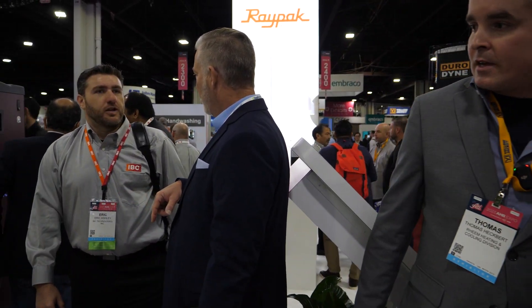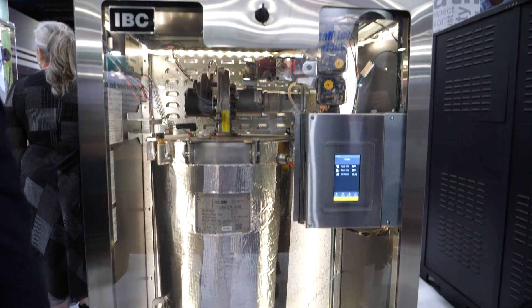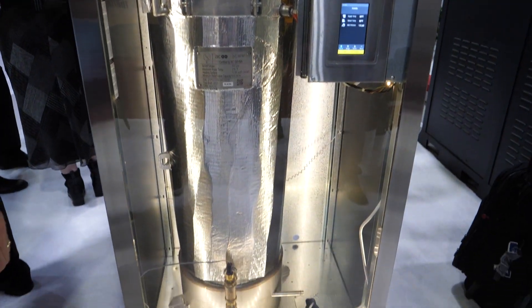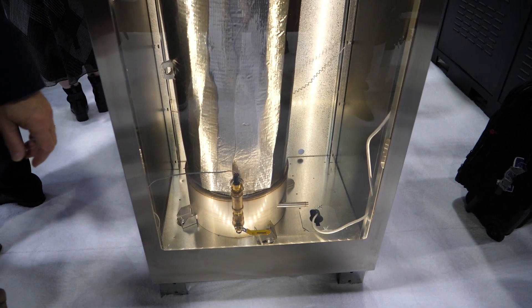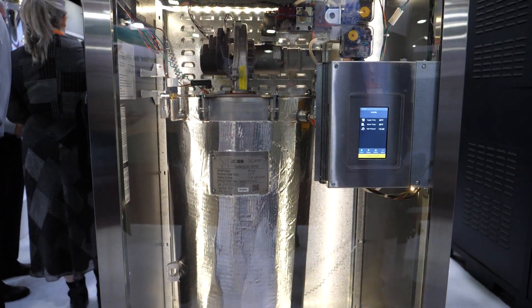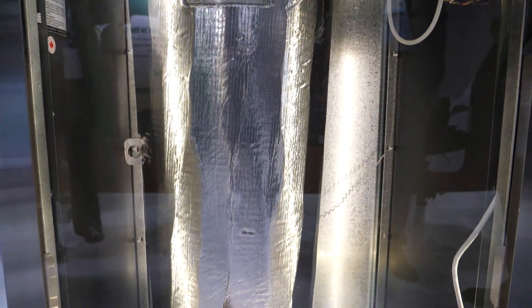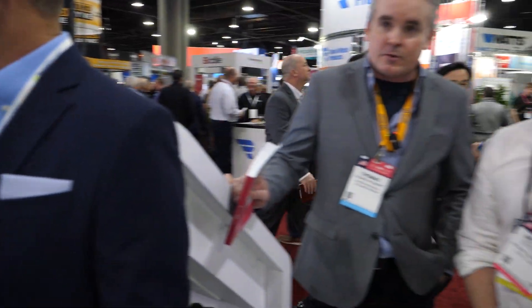The EX series has been on the market for about two years and has been working extremely well. It uses the same V10 basic control, except these all come BACnet-enabled, so you're ready to connect to a building management system — less relevant for residential but very important on commercial. There's a 400 model at 399,000 BTU/hr which falls under the ASME code restriction, and then the 500 and 750 are all ASME-ready with all the proper safeties, lockouts, and controls.